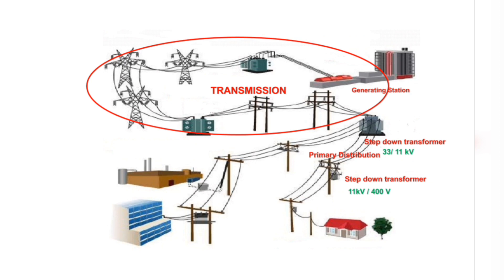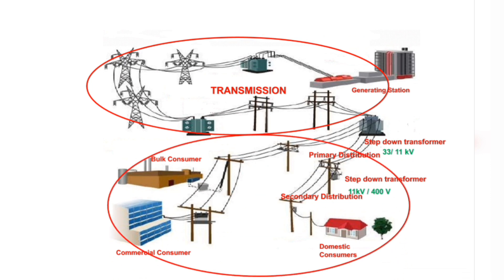From the distribution step-down transformer of 11 kV/400 V, the power is distributed to various consumers like domestic consumers, bulk consumers, and commercial consumers. If the required power of industrial consumers is very high, they are considered bulk consumers, and power is directly fed from the 33/11 kV transformer. The primary distribution and secondary distribution together constitute the distribution system, which is next to the transmission system and supplies power to end users.